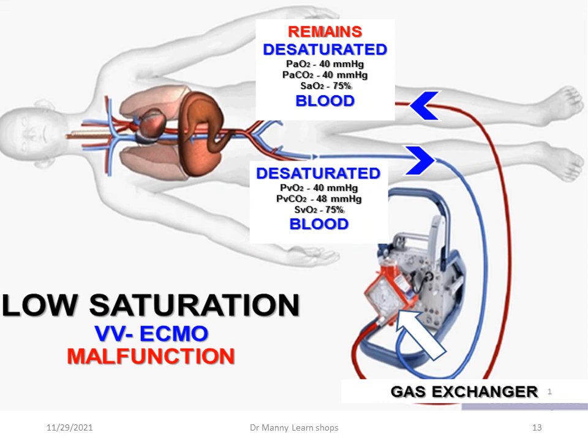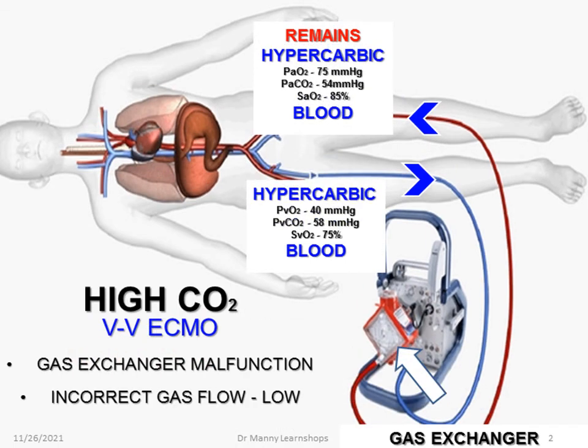It can also be malfunction. So if your gas exchanger is malfunctioning, you're going to get a low saturation. High CO2 can be the result of gas exchanger malfunction again, or you've got the incorrect gas flow. It's too low. Remembering that oxygen flow into the exchanger will increase CO2 removal if you've got a high flow, or it won't allow excretion effectively if it's too low. So incorrect gas flow or malfunction in the exchanger.